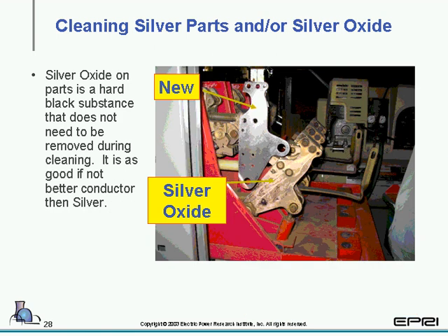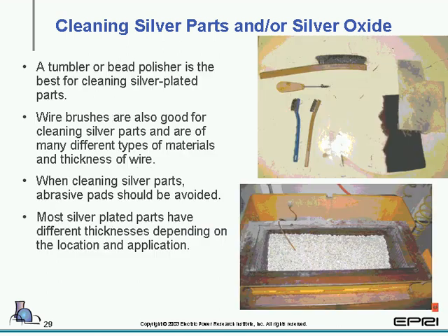Cleaning silver parts. We actually have a new part and a silver oxide. Now, silver oxide is as good of a conductor, if not better, than silver itself. And for those taking the test, you might want to remember that. Silver oxide is as good of a conductor, if not better, than silver itself. So it's important to remove the old lubricant, but not necessarily the silver oxide.